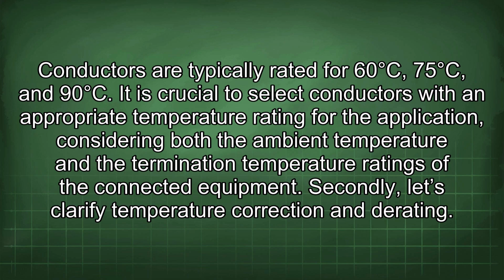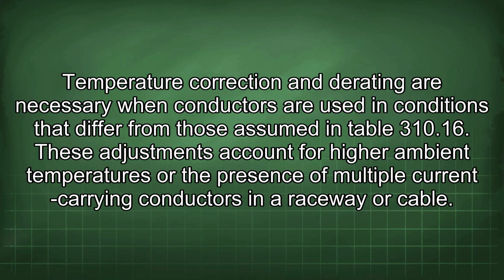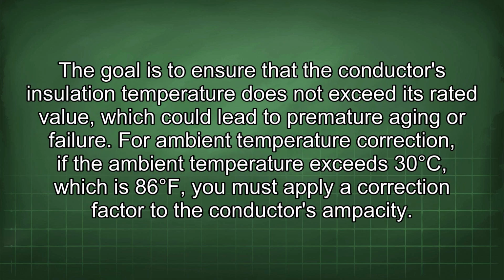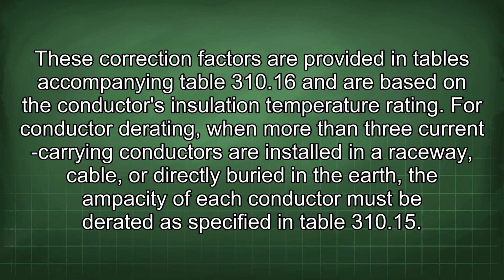Secondly, let's clarify temperature correction and derating. Temperature correction and derating are necessary when conductors are used in conditions that differ from those assumed in Table 310.16. These adjustments account for higher ambient temperatures or the presence of multiple current-carrying conductors in a raceway or cable. The goal is to ensure that the conductor's insulation temperature does not exceed its rated value, which could lead to premature aging or failure. For ambient temperature correction, if the ambient temperature exceeds 30 degrees C, which is 86 degrees F, you must apply a correction factor to the conductor's ampacity. These correction factors are provided in tables accompanying Table 310.16 and are based on the conductor's insulation temperature rating.